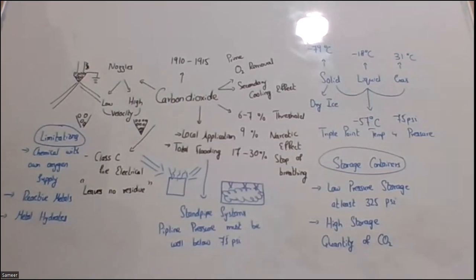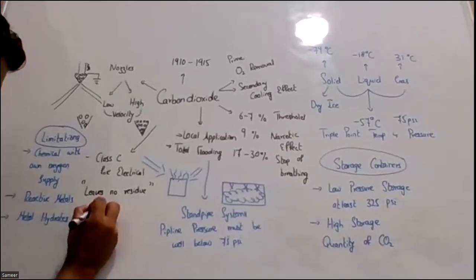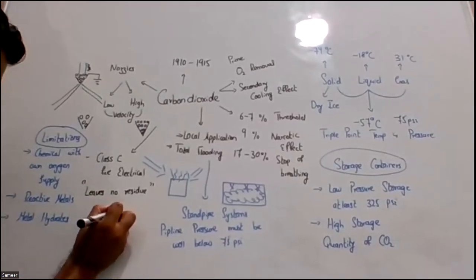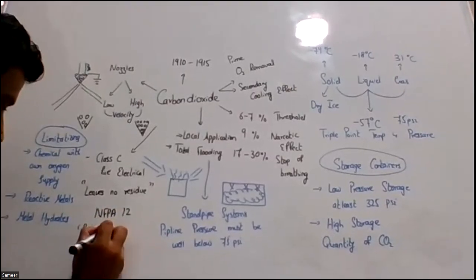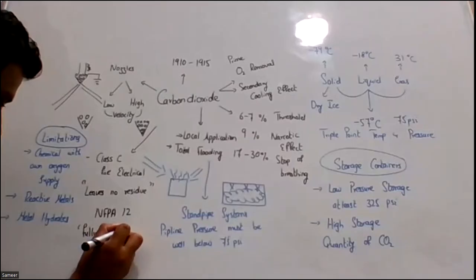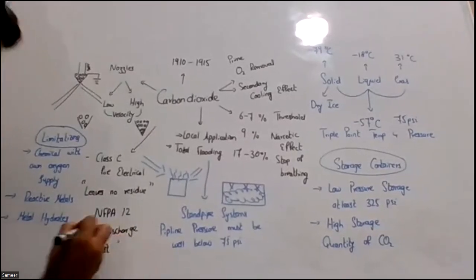NFPA 12 requires, for the carbon dioxide system, that whenever a new system is installed, a full discharge test is required.